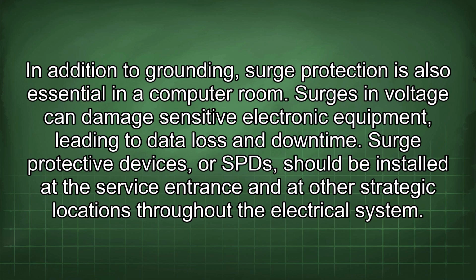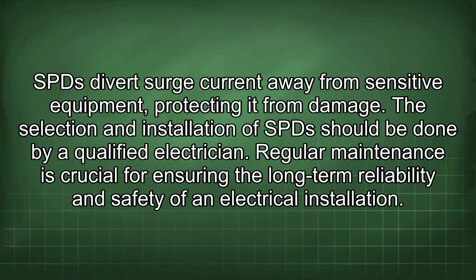In addition to grounding, surge protection is also essential in a computer room. Surges in voltage can damage sensitive electronic equipment, leading to data loss and downtime. Surge protective devices, or SPDs, should be installed at the service entrance and at other strategic locations throughout the electrical system. SPD diverts surge current away from sensitive equipment, protecting it from damage. The selection and installation of SPD should be done by a qualified electrician.